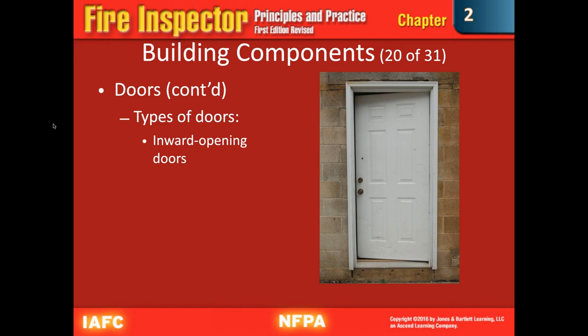Anybody heard of the Station Nightclub fire other than my passing mention of it earlier? Yes, I did a case study on it once. Okay. So in regards to the door, the main doors to go into the building itself were double doors like any other commercial building. Fantastic, right? But when you got into that first area, they had a little foyer, where somebody checked and got the cover charge. And then you went through a door like what's in that picture to get to the rest of the club, and it opened in. That was not part of the original building; it was added on. It was one of the many things wrong with that place.